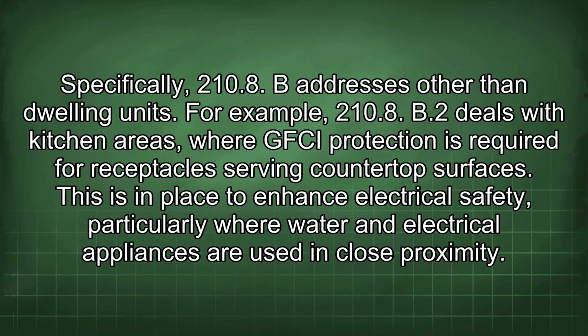Specifically, 210.8(B) addresses other than dwelling units. For example, 210.8(B)(2) deals with kitchen areas, where GFCI protection is required for receptacles serving countertop surfaces. This is in place to enhance electrical safety, particularly where water and electrical appliances are used in close proximity.